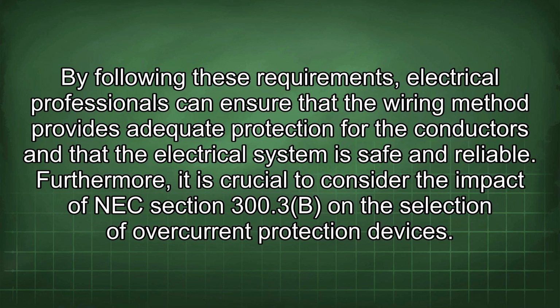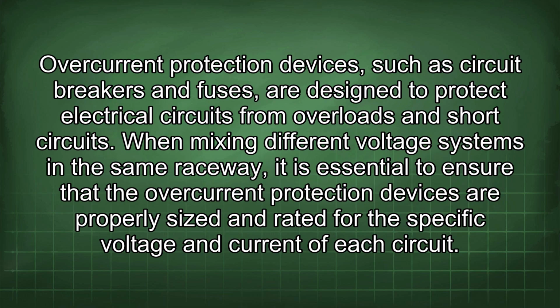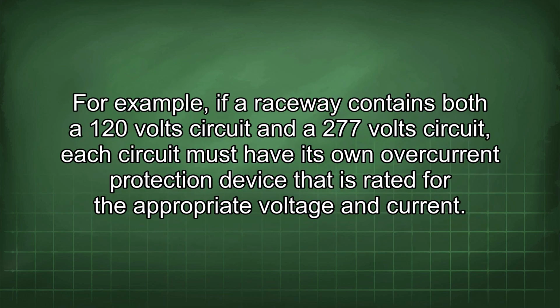Furthermore, it is crucial to consider the impact of NEC Section 300.3b in the selection of overcurrent protection devices. Overcurrent protection devices, such as circuit breakers and fuses, are designed to protect electrical circuits from overloads and short circuits. When mixing different voltage systems in the same raceway, it is essential to ensure that the overcurrent protection devices are properly sized and rated for the specific voltage and current of each circuit. For example, if a raceway contains both a 120-volt circuit and a 277-volt circuit, each circuit must have its own overcurrent protection device that is rated for the appropriate voltage and current.